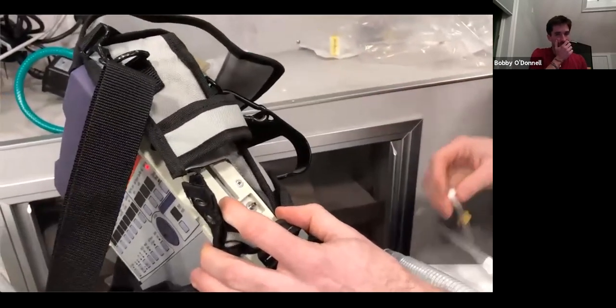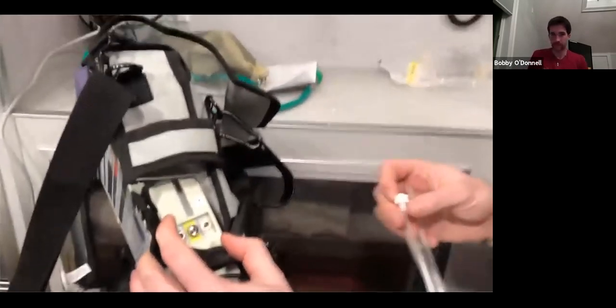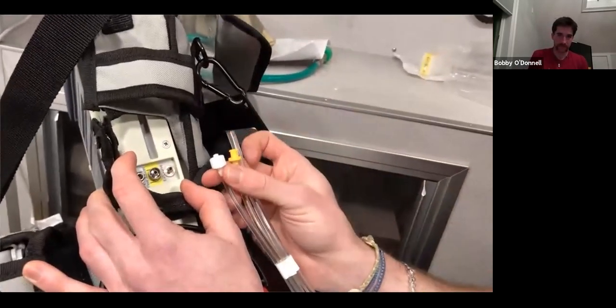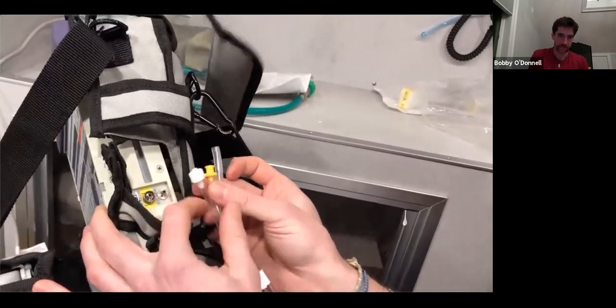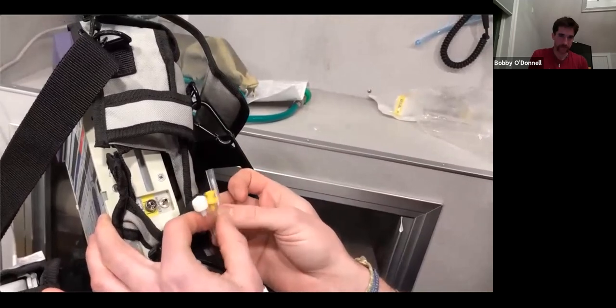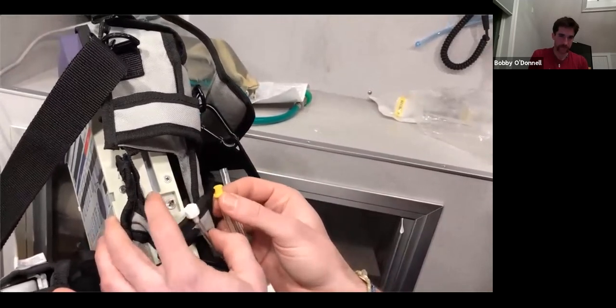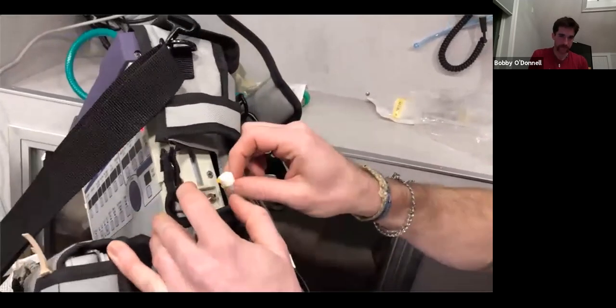So there are ports right here, and these are super important because these are our pressure transducers. So not that it matters, but white is the high transducer, yellow is low, and then that's the exhalation valve there. But generally all of our alarms, this is one of the first things you should check is these connections for your low pressure, high pressure alarms.